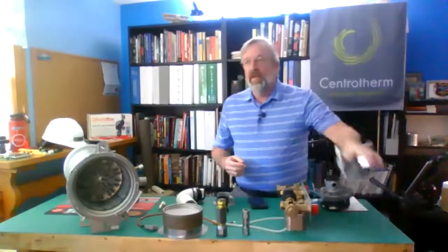So some of the things that we can run into there are, we're looking for air, fuel, and spark. So usually the first thing I recommend people do is make sure they have fuel. And that's this guy right here. That's this gas valve. So we want to troubleshoot that. The very first thing that we're going to do is there are two test ports you can see right here. I've got an inlet, and basically I have a positive on this side, and I have a negative on the other side.